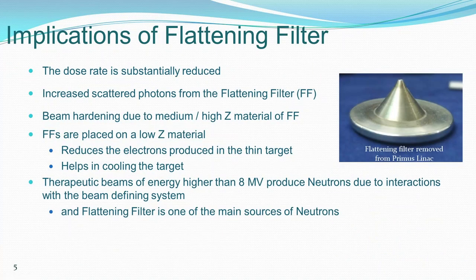What are the implications of having a flattening filter? This is an actual flattening filter I personally removed from a Primus linear accelerator. When you introduce this in the beam path, the dose rate is substantially reduced. There is increased scatter from the flattening filter, and the beam is hardened as soft X-rays are cut off. It is also placed on a low-Z material which helps cool the target. For beams above 8 MV, photonuclear interactions produce neutrons, and the flattening filter is one of the main neutron sources.